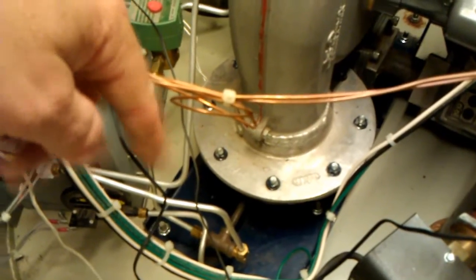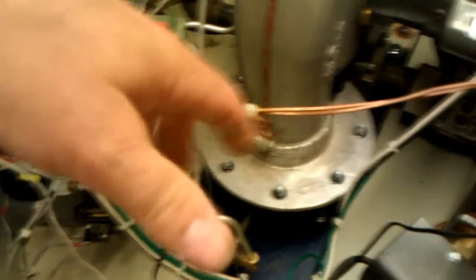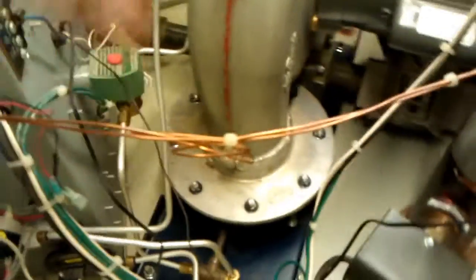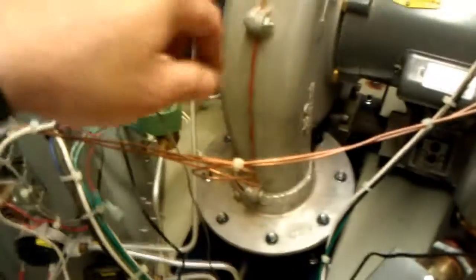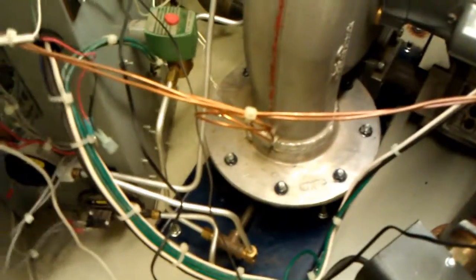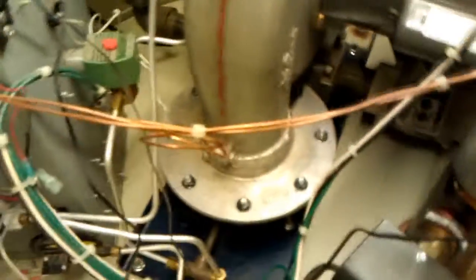There's a fine screen before that mesh. It's actually not the heat exchanger, the burner is a wire mesh, but there's a screen before that. Sure enough, it was starting to trip one of those pressure switches and I had to diagnose it. It only did it when it ramped up the modulation for more capacity.